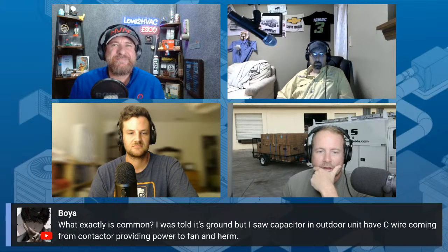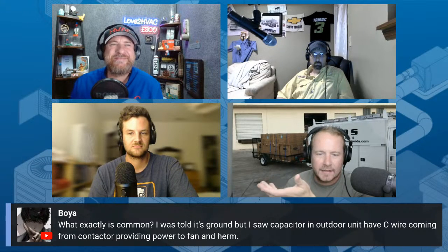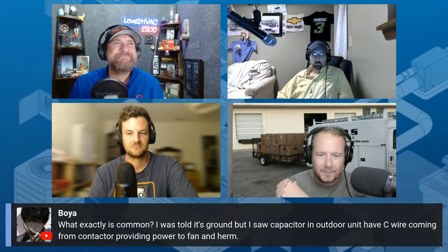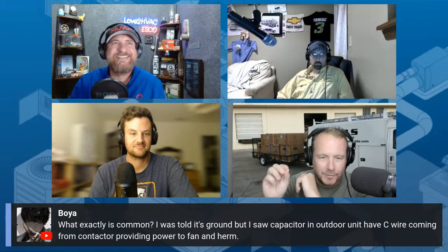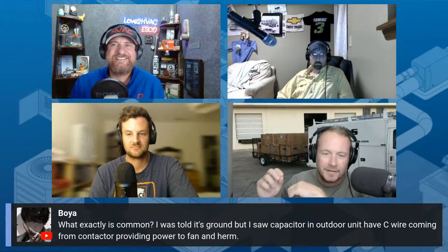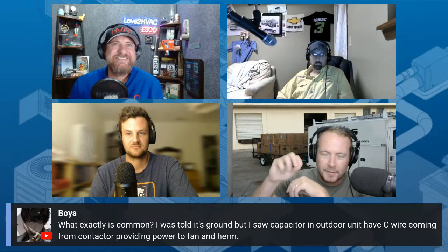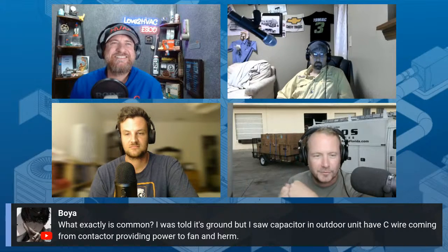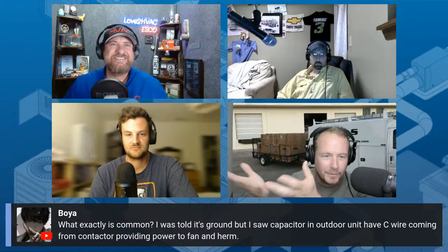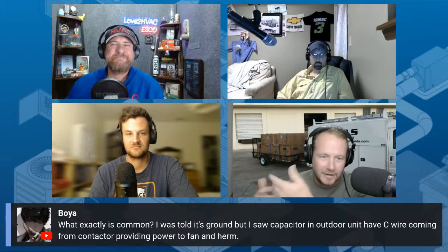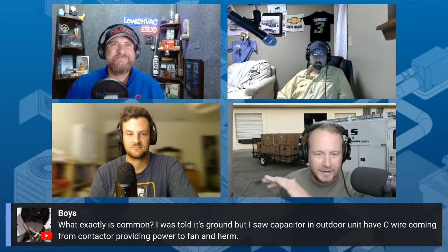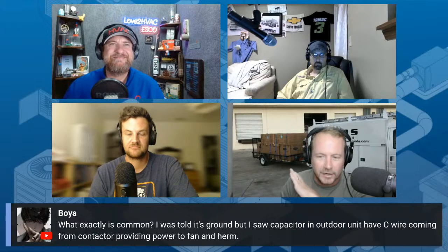Yeah, for sure. It just means it has something in common, like you said. Common on the compressor is the common terminal between start and run. Common on low voltage means the common point everything returns to on the other side of the transformer. Like you mentioned, the capacitor has a common point between the two capacitors. It means something different in every single application, so just recognize it's not a universal term.